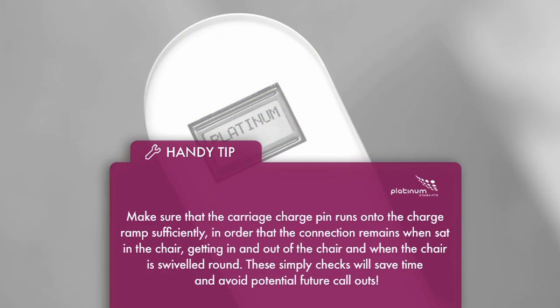Handy tip: Make sure that the carriage charge pin runs onto the charge ramp sufficiently in order that the connection remains while sat in the chair, getting in and out of the chair and when the chair is swiveled round. These simple checks will save time and avoid potential future call outs.